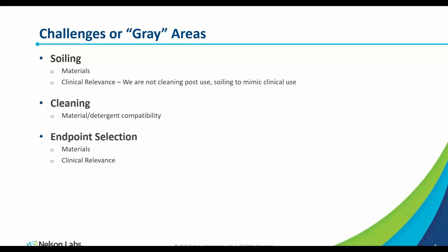And clinical relevance. To align with ST98 and the FDA guidance, you should really select endpoints that are clinically relevant. But in this case, I think for 3D printed devices, looking at protein, total organic carbon, and cytotoxicity post-cleaning are good endpoints to select, especially because protein is kind of a catch-all endpoint. Total organic carbon is great because it is also used for manufacturing residuals, so it can be kind of a win-win situation. You can knock out one of your manufacturing residual tests and combine them into this test plan for these types of validations.